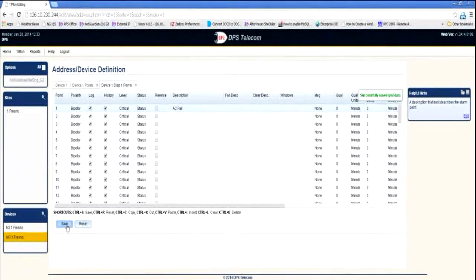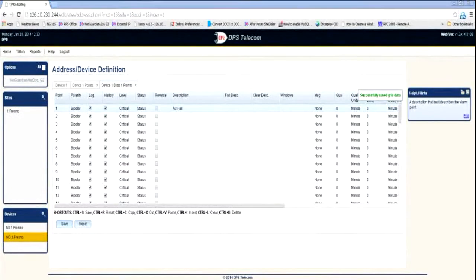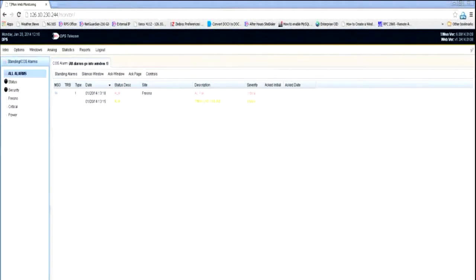That's really all that's involved to see the event on the included Web Monitor interface. The change of state, or COS list shown here, provides complete visibility when the alarm comes in and also when it clears. The events are removed from the COS list only when they are specifically acknowledged by one of your operators.